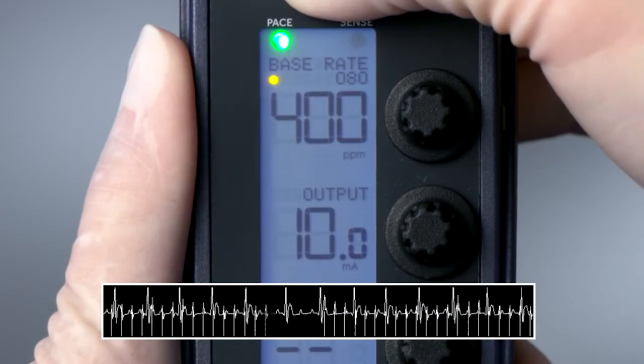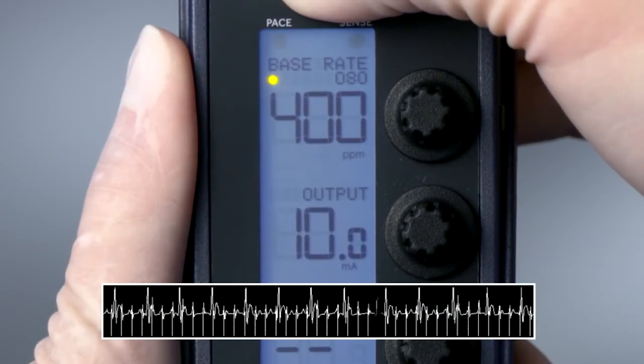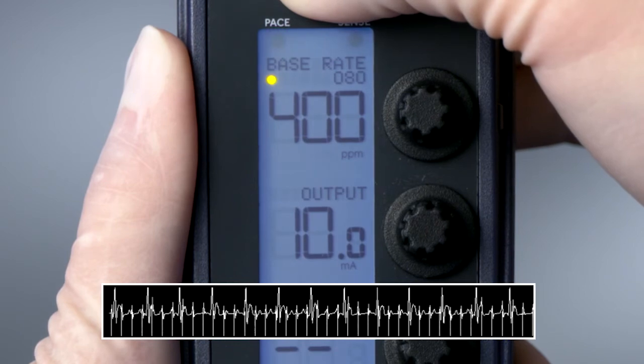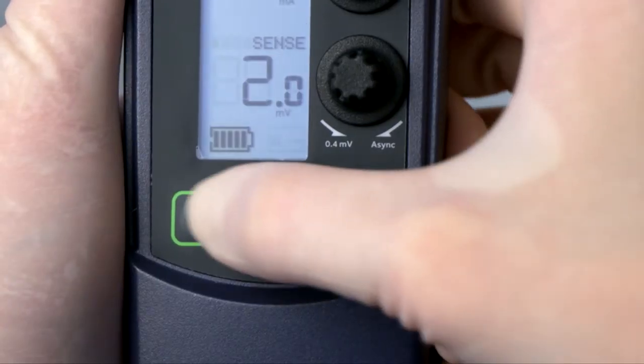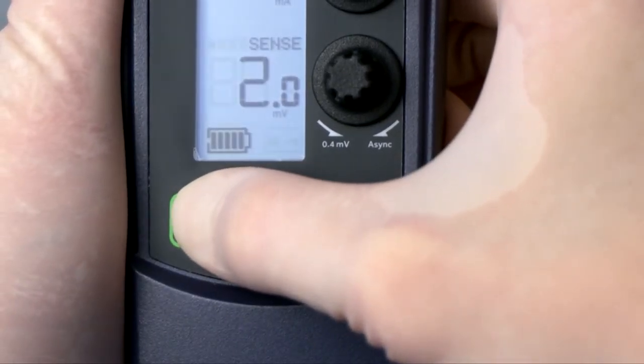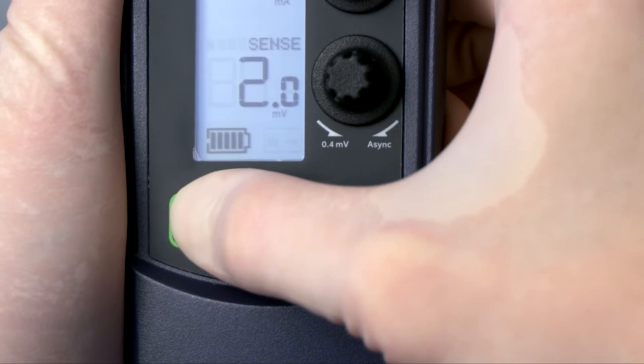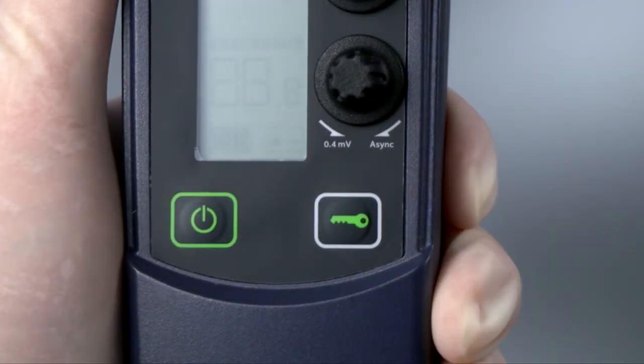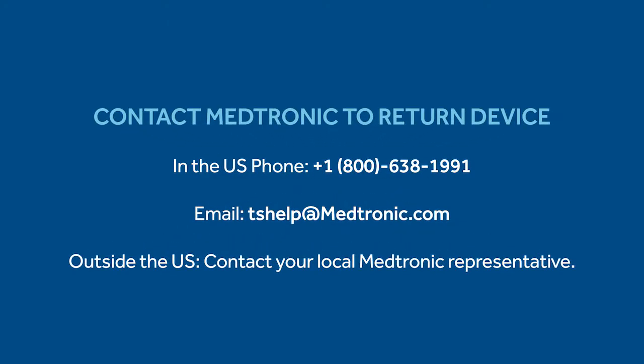If the temporary pacemaker continues to deliver Rapid Atrial Pacing after the Hold to Deliver button is released, press and hold the On-Off button to stop Rapid Atrial Pacing. If Rapid Atrial Pacing continues to be delivered, remove the batteries from the temporary pacemaker and return the temporary pacemaker for service.